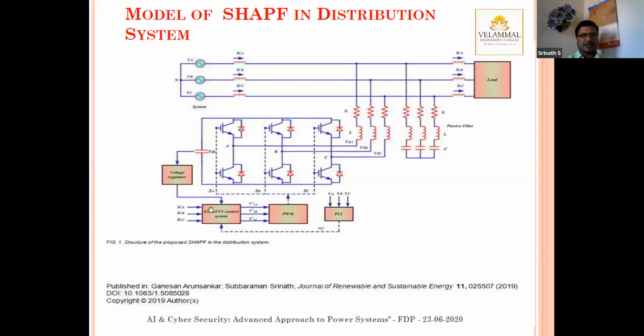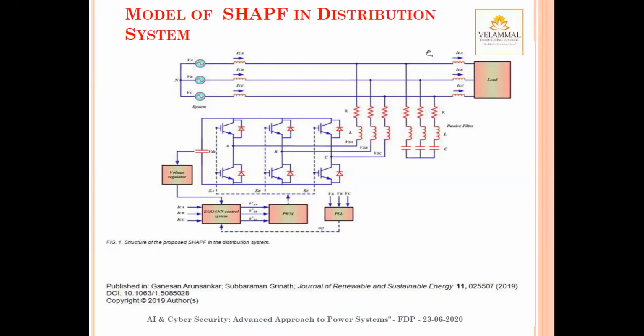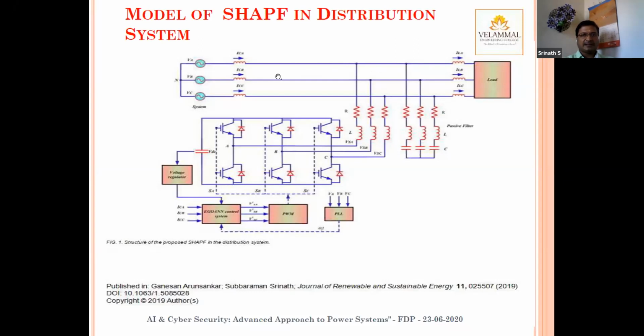It gives input to the controller, which further decides the voltage, because you can see this is having a harmonic. When this is a harmonic current, the same harmonic will get reflected in the source current. So when I measure the source current, I can find out what negative harmonic needs to be injected from here. When I inject negative harmonics into the system, the positive and negative harmonic currents cancel, and finally the current flowing into the source will be completely harmonic free.